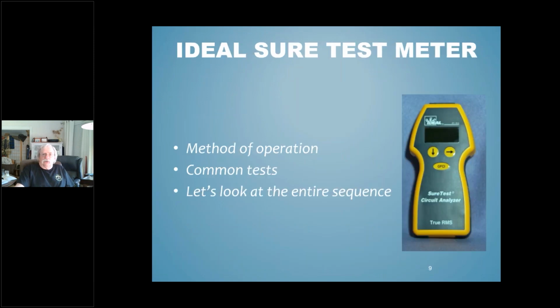Let's start out with the SureTest, because it's one of the most comprehensive test tools out there, and it's incredibly easy to use once you understand what some of its limits are. To begin, you're going to need to make up some adapters because it comes with a 15 amp plug. So you're going to need a 15 to 30 amp, and you may have to make up a couple of adapters if you're going to be working with 240 volts: L1, neutral and ground, L2, neutral and ground, separated out with two adapters so that you can plug the 15 amp attachment cord into that and take some measurements.